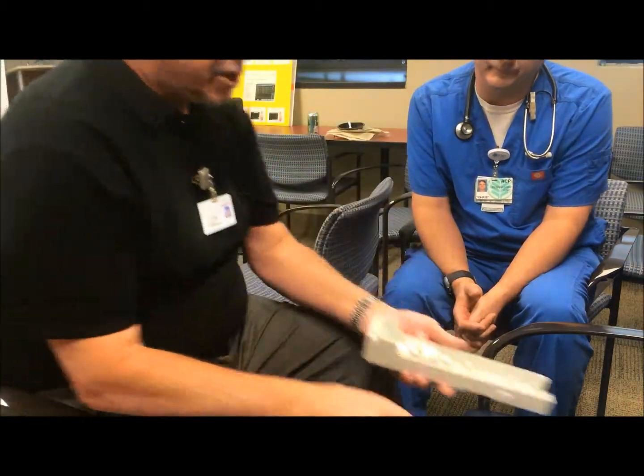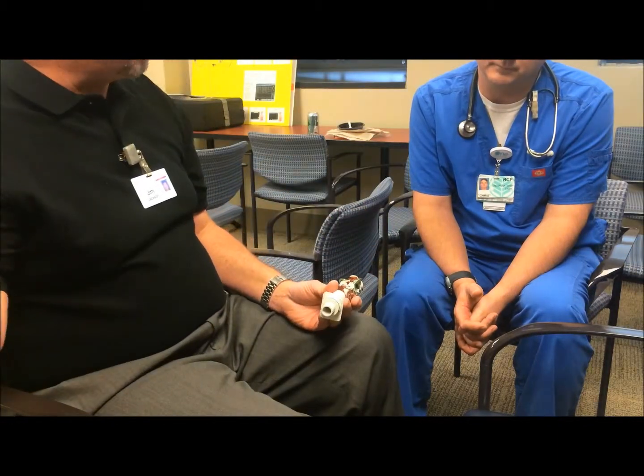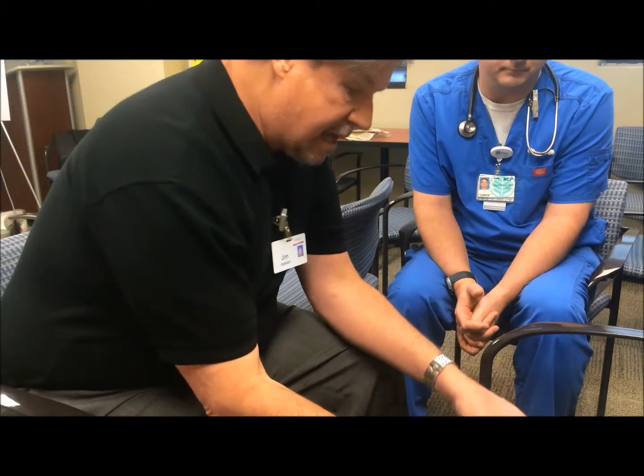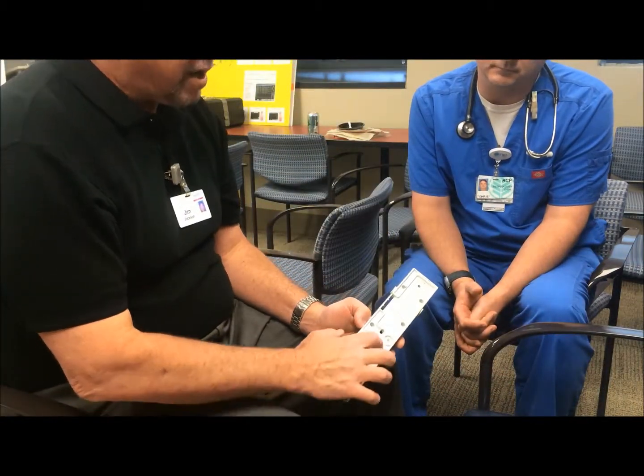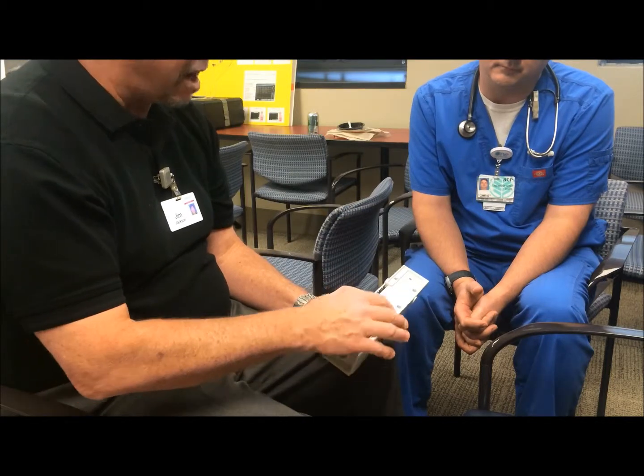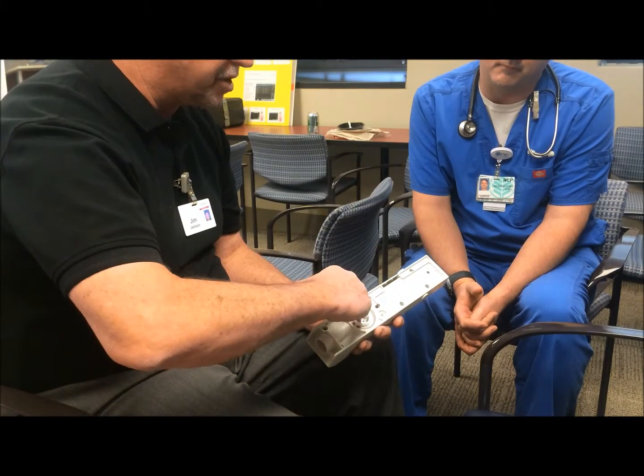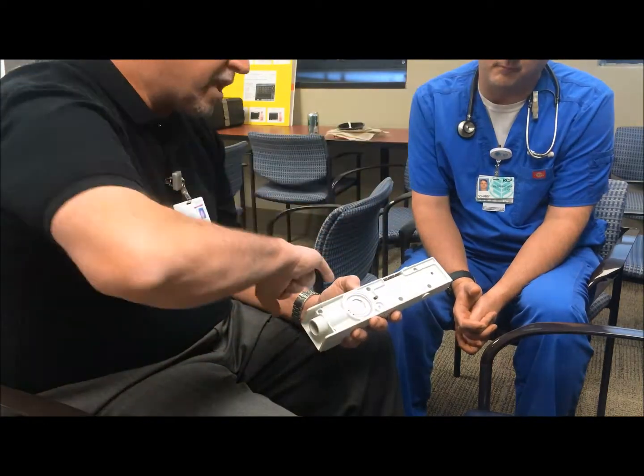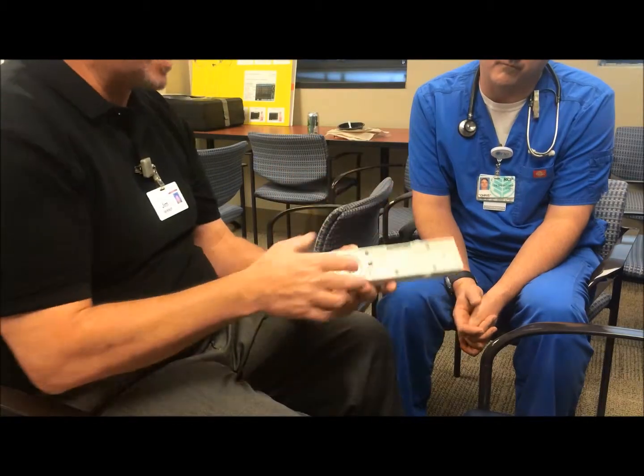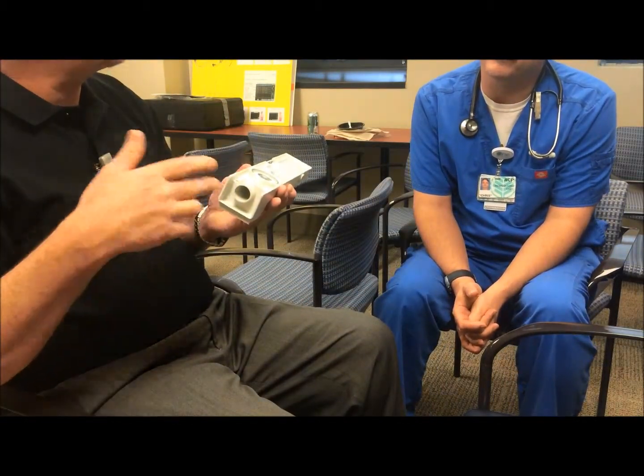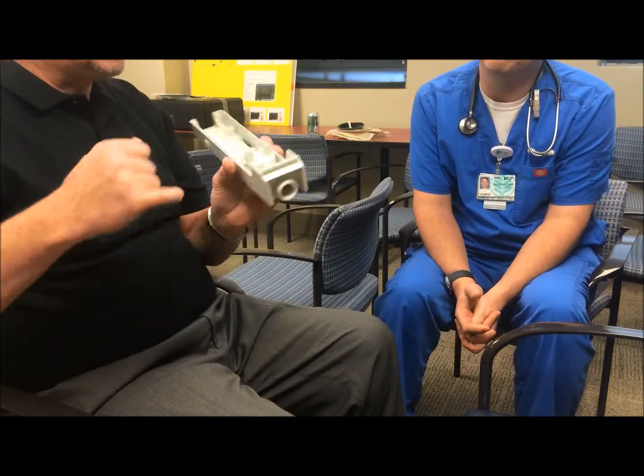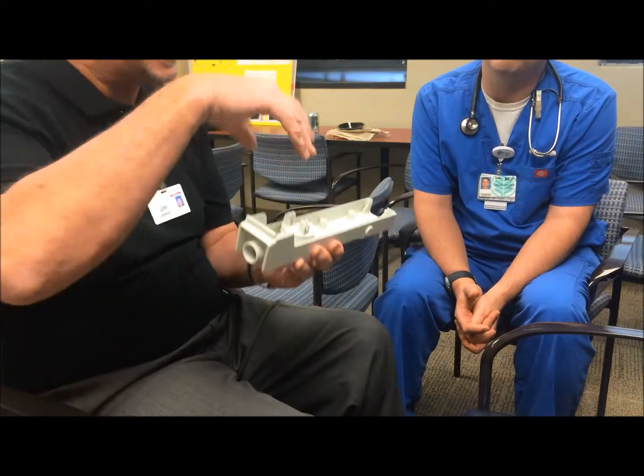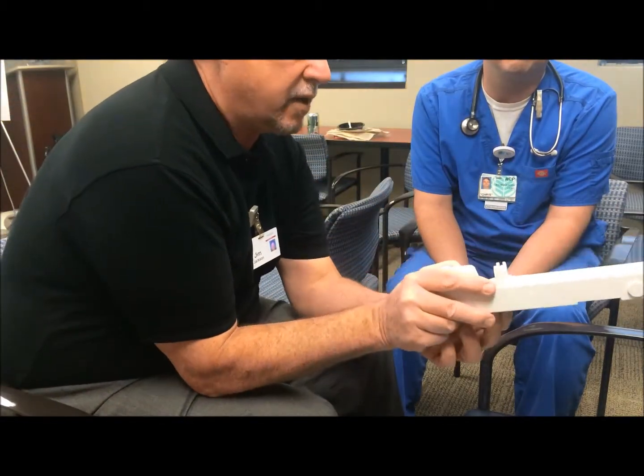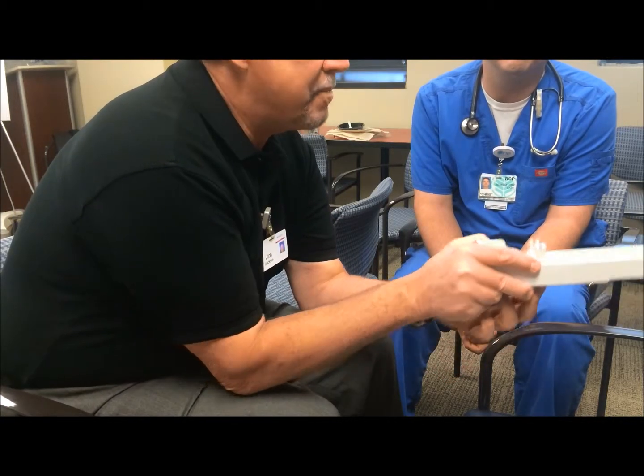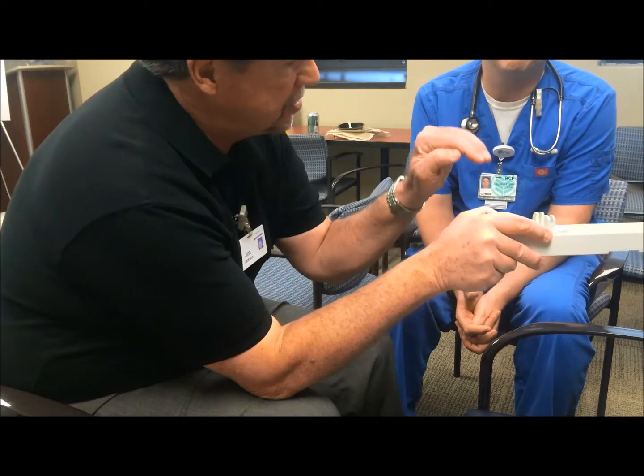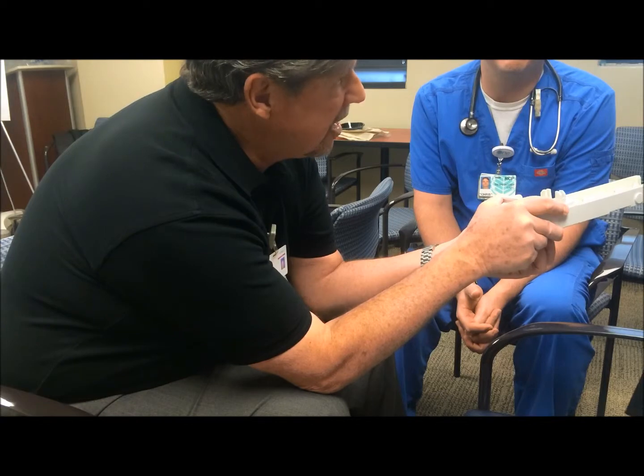Okay, so the two parts that could leak are that moisture trap I told you about, and also the membrane. The leakage wouldn't necessarily come from here, like you were saying, where you just wipe it off. It's not really that, because the only thing that hits this is just a little stem. But in principle, if you put your finger on the inside of that, you might find that if you do a lot of nebulizer treatments and don't clean the cassettes, sometimes crystals can form on the inside of that membrane. I'll show you, when you push up on it, you see that. There might be one little teeny crystal that causes a little bump, and so gas leaks out when that closes.